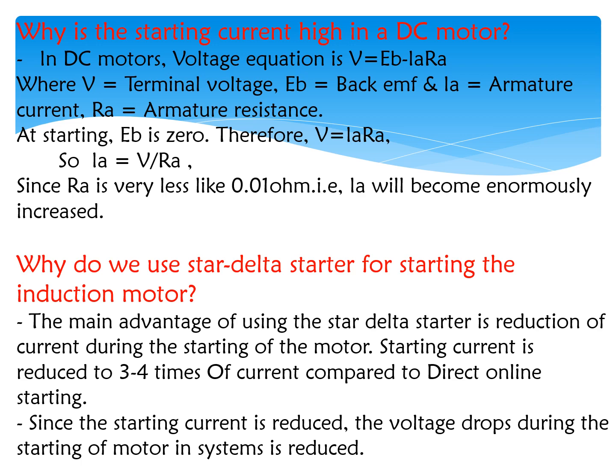Why do we use a star delta starter for starting of the induction motor? The main advantage of using the star delta starter is the reduction of starting current of the motor. Starting current gets reduced minimum 3 to 4 times compared to direct online starting. Since the starting current is reduced, the voltage drop during the starting of the motor in the system is also reduced.